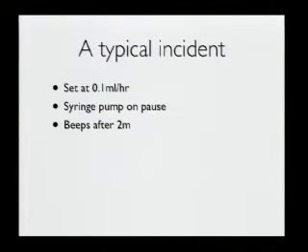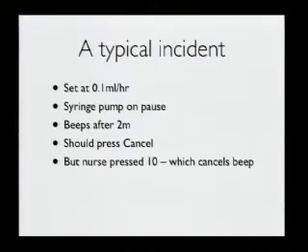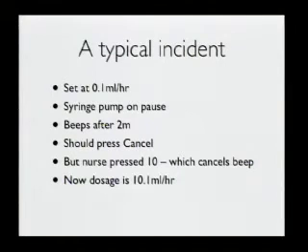So it makes sense. But in this case, it was distracting the doctor and nurse, and the doctor told the nurse to switch it off. She should have pressed cancel. You can imagine you're dealing with a premature baby and you reach over and press the button. In fact, she pressed 10, and 10 cancelled the beeping. And now the dosage was 10.1 mils per hour, and it started pumping. And 10, 15 minutes later, the baby was dead. And you can imagine, you believe you've just switched off the syringe pump. So when the baby starts getting distressed, it's the last thing you think of, and you end up killing them.